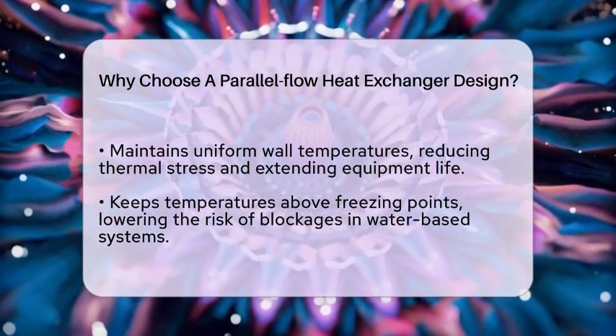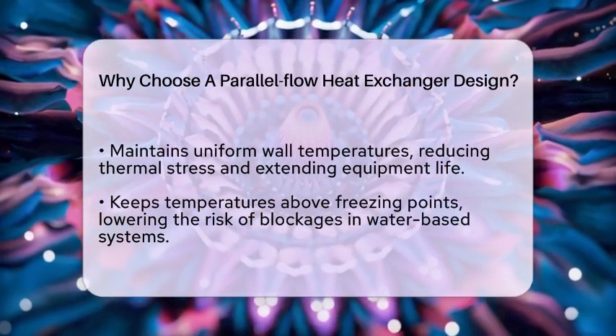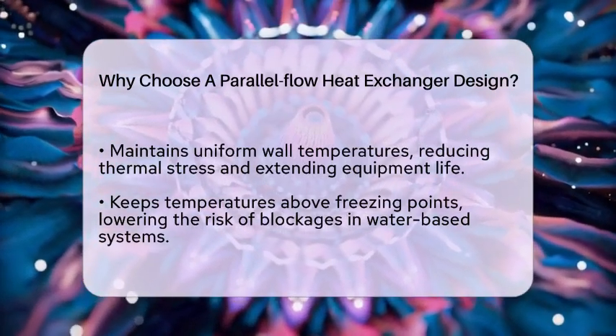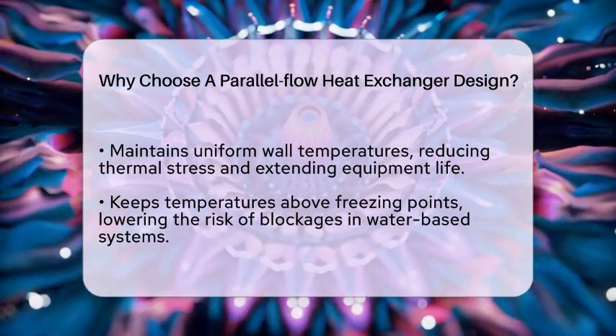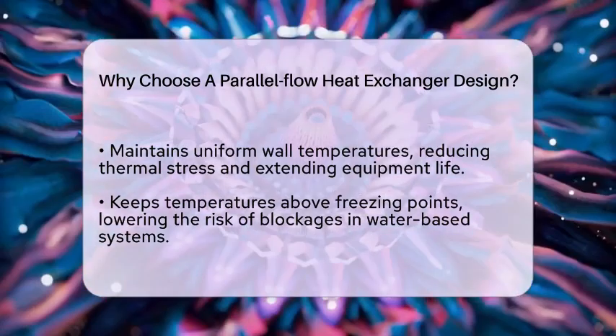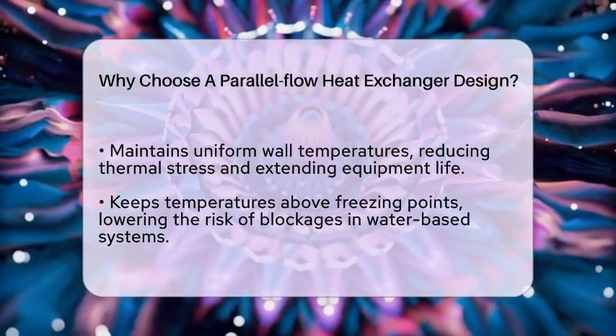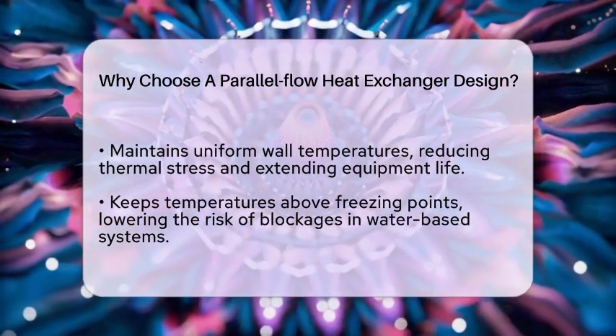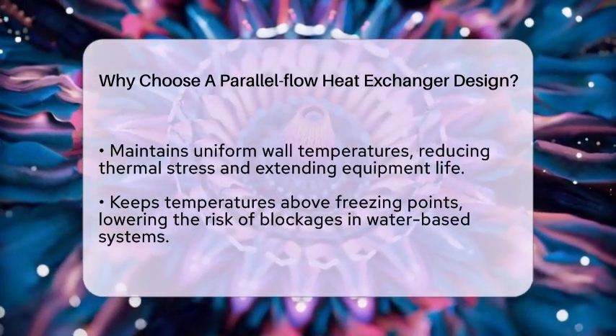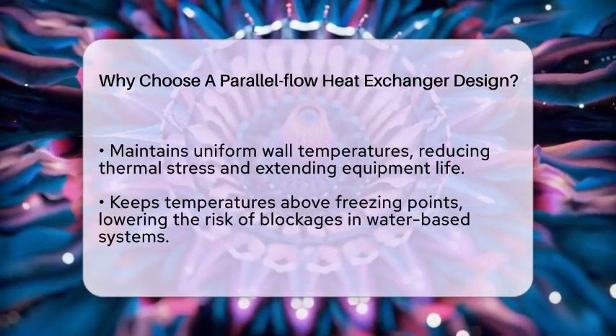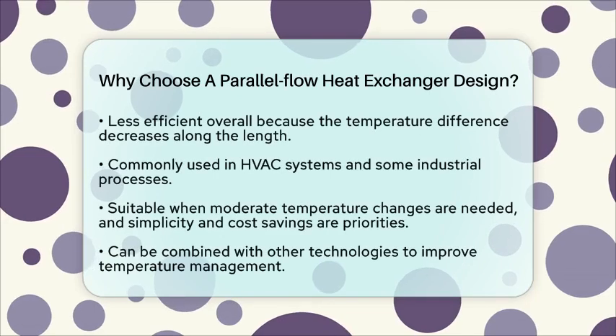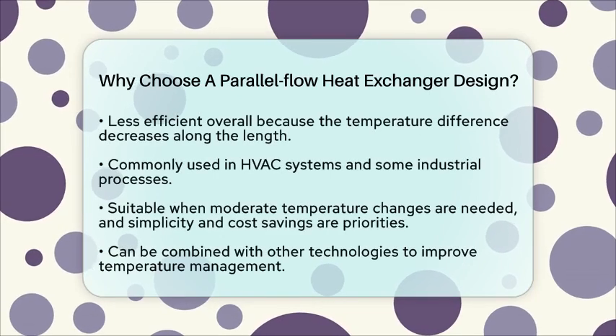However, it's important to remember that parallel flow isn't perfect for every situation. Because the temperature difference between the fluids decreases along the length of the heat exchanger, the overall heat transfer efficiency is lower than in other designs. If you need a large temperature change for both fluids, a different setup might be better.